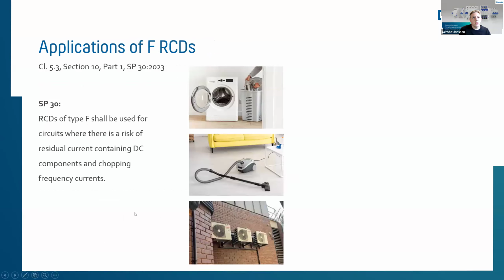Coming back to applications for type F RCDs, as per the electrical code, the RCDs of type F shall be used for circuits where the risk of residual currents is meanwhile containing DC components, coming out of those single-phase frequency drives like washing machines, vacuum cleaners, here as well air conditionings. In Germany, the counterpart is meanwhile a heat pump coming up more and more on the market. So we are talking about one-phase plus neutral applications with DC components in it, which every normal modern household will show up meanwhile.